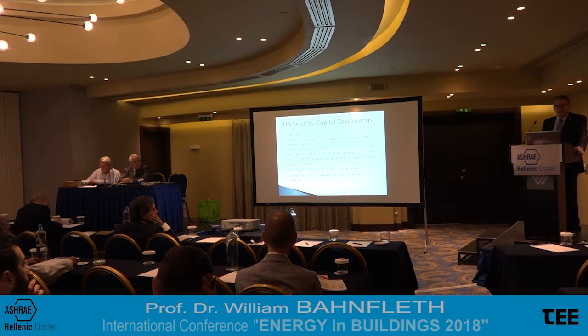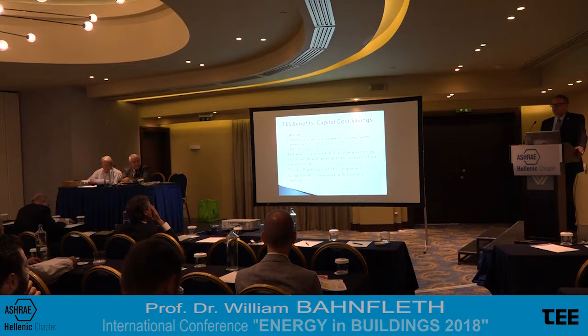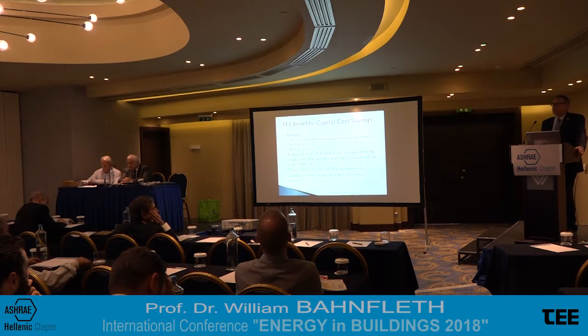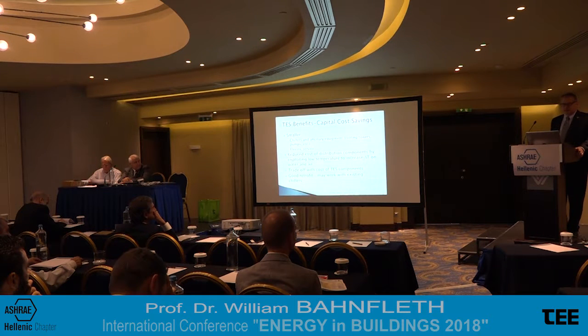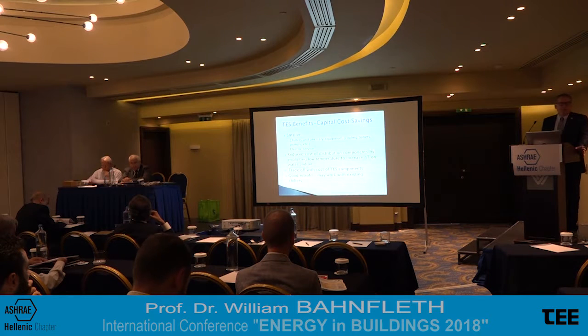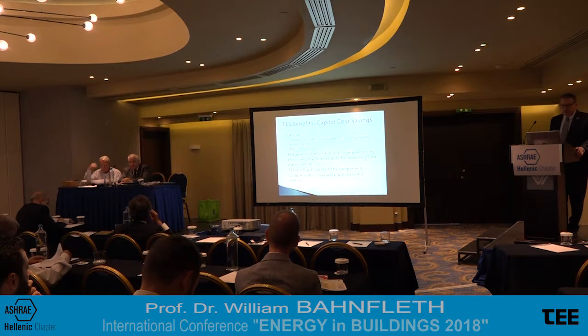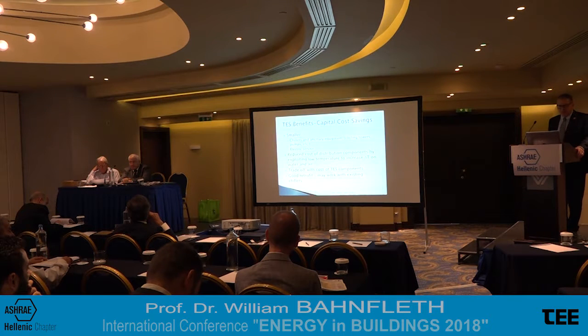The other potential savings from thermal storage are capital cost savings, because when we take advantage of load shifting to make the peak load smaller, then many things are smaller and less expensive. So chillers and their ancillary equipment, cooling towers, pumps, piping get smaller, maybe the electric service. And if we have a cold source, if we're using ice storage, for example, then it's possible to make lower temperature water and air distribute, which may reduce the distribution energy as well as the cost of ductwork and piping.